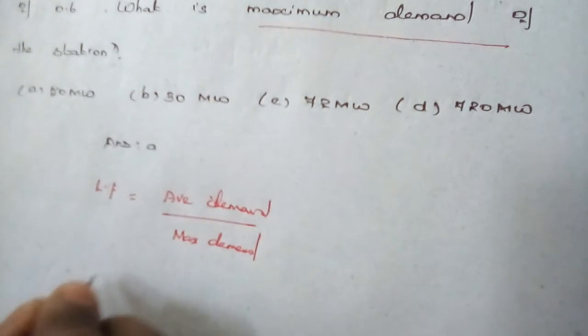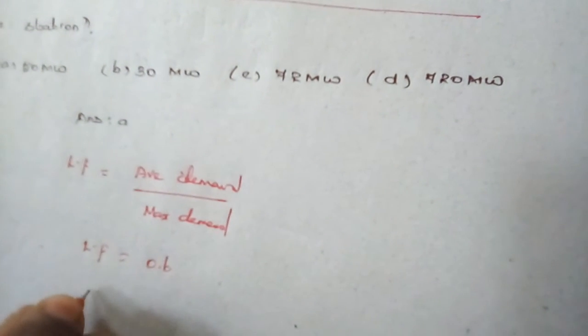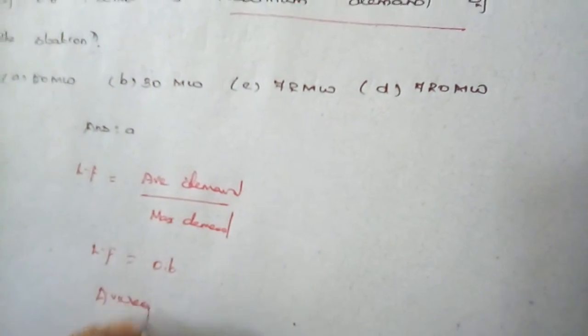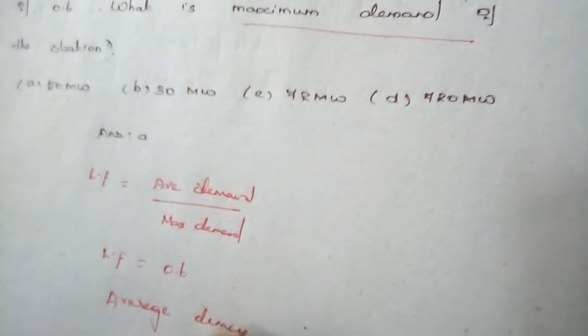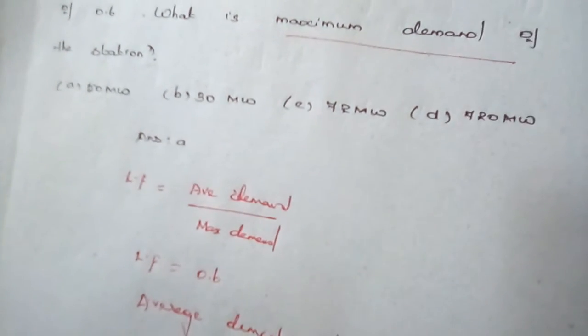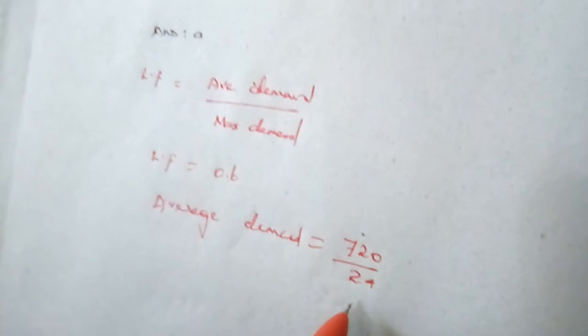Given: load factor equals 0.6. First, find the average demand: average demand equals daily energy produced divided by 24 hours. The daily energy produced is 720 megawatt-hours, so average demand equals 720 divided by 24, giving a value of 30 megawatt.